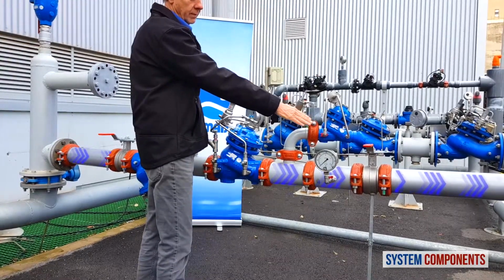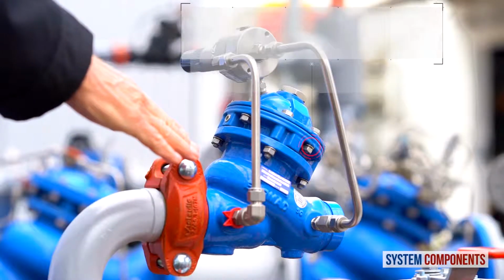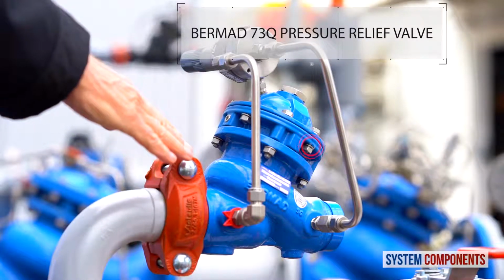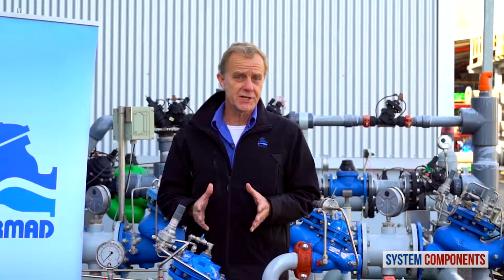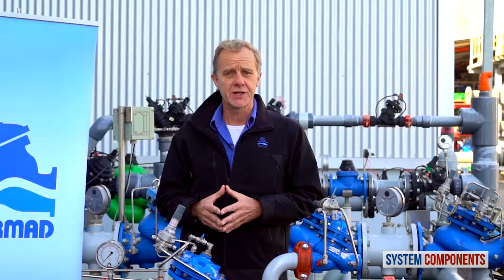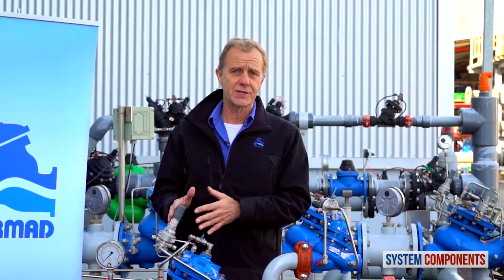Downstream of the pressure reducing valve, we have a pressure relief valve that will open to prevent any overpressure to the consumer line. Also in this installation, we have two pressure gauges, upstream and downstream of the 720 pressure reducing valve.